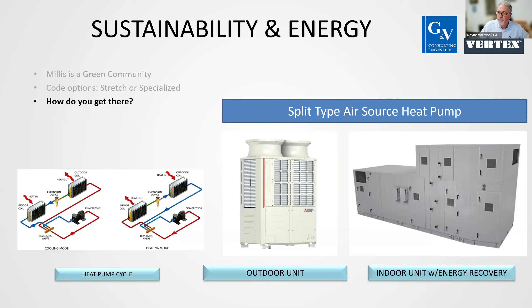We talk about air source heat pumps a lot, and they come in all shapes and sizes. The VRF system that we were talking about earlier, and then we have these packaged units. They look like normal rooftop units that you see on any building, any school, except instead of having a hot water and a chilled water coil, they would use the heat pump cycle. They have energy recovery components built into them. On the diagram on the right, the cutaway view, you can see the segmented wheel in the right-hand corner of the unit. Air being exhausted out of the building passes through that wheel as it rotates, and it's got a plastic-based material that absorbs heat and moisture.